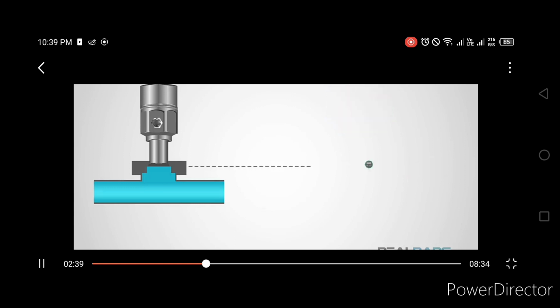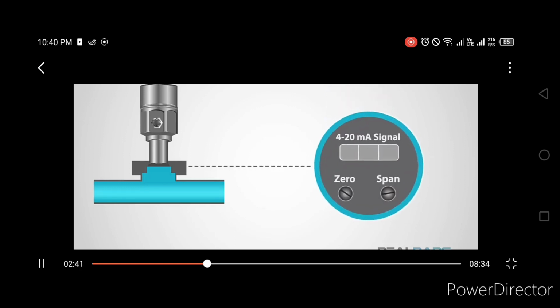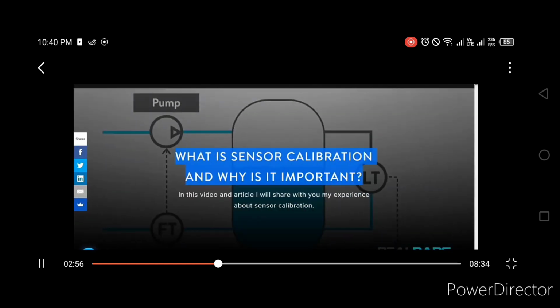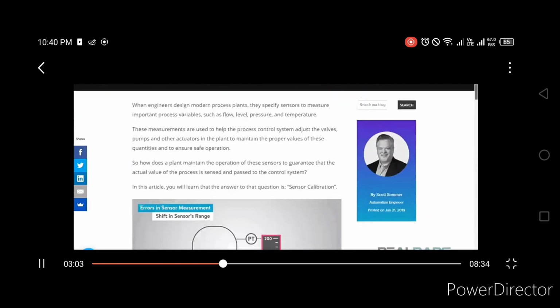Pressure sensors need to be calibrated so they know what voltage or milliamp signal corresponds to what pressure. This is a basic zero and span calibration, or minimum and maximum, which is a common job for maintenance personnel. In the RealPARS video, What is Sensor Calibration and Why is it Important?, we describe sensor calibration in detail.